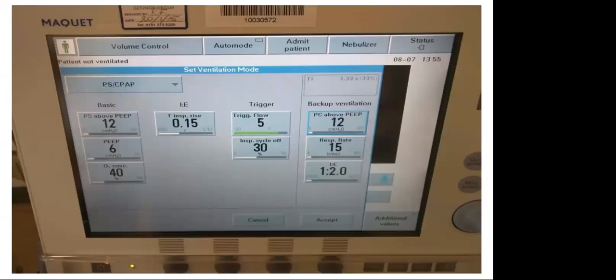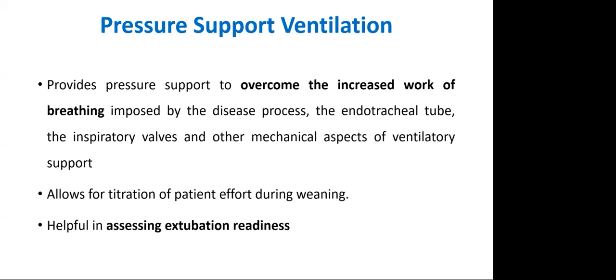SIMV will synchronize during the SIMV period, and it will decrease the asynchrony. That is the main thing. And during the spontaneous period, if the child is breathing, it will allow the patient to generate the flow. But if you want to support that also, that is called SIMV with pressure support. You can support the in-between breaths also. You can see here, this is the machine breath given by the SIMV, and this is the spontaneous breath which the child is taking in between. That can also be supported by using SIMV pressure control or volume control with pressure support.